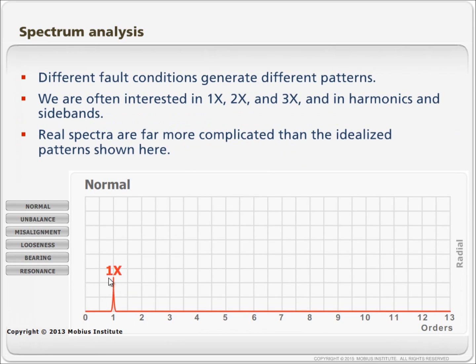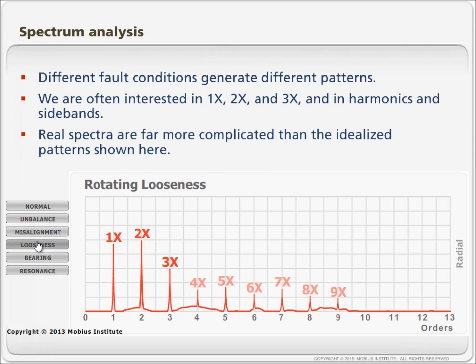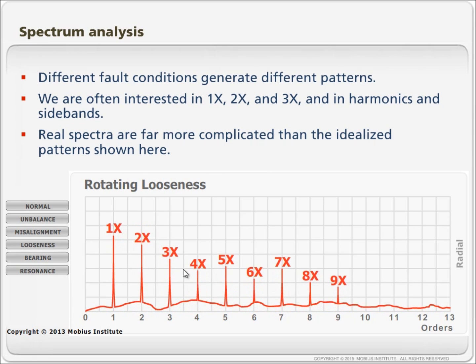If the vibration was normal, we always expect some vibration at the running speed. But in an ideal world we would not see any other vibration. If there was unbalance though, that vibration would be higher. If there was misalignment, we might see 2x or 3x or 4x or 5x. That's a different story. Looseness, for rotating looseness, we might see lots of these peaks which are called harmonics.